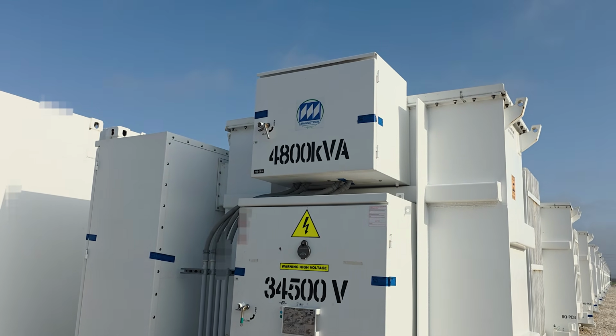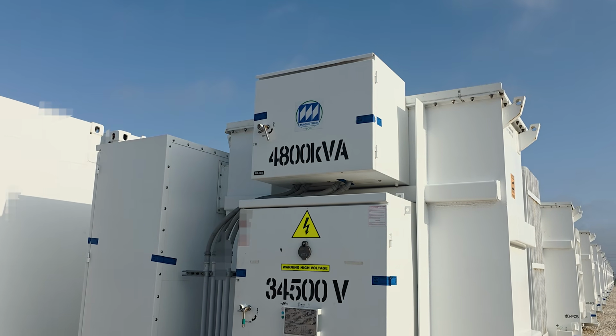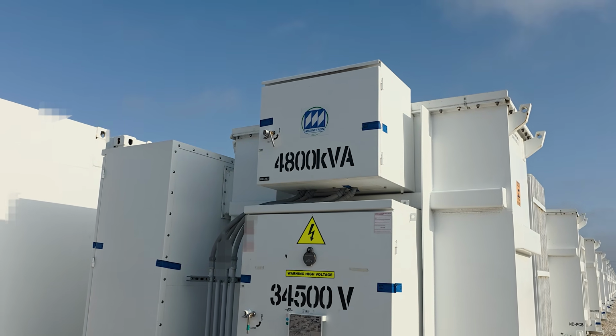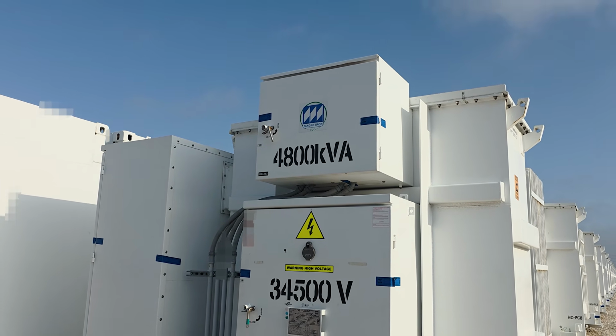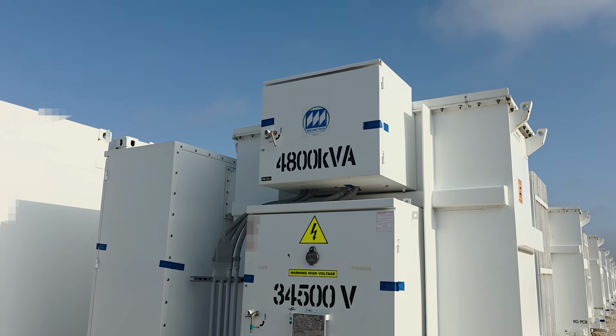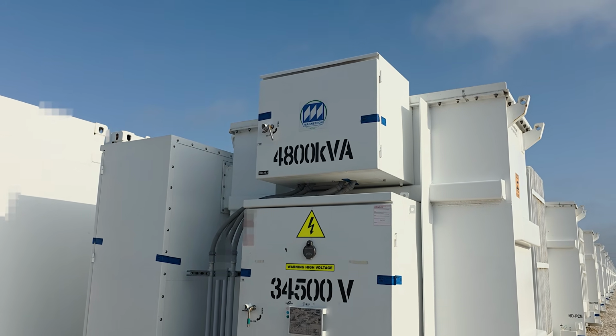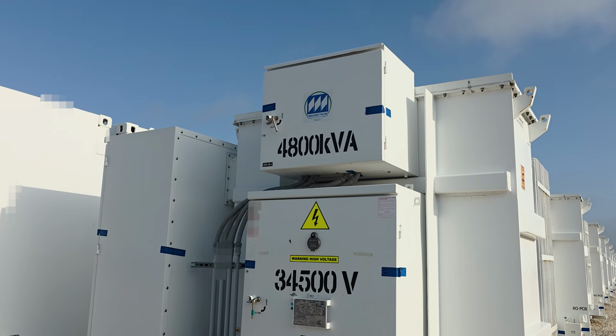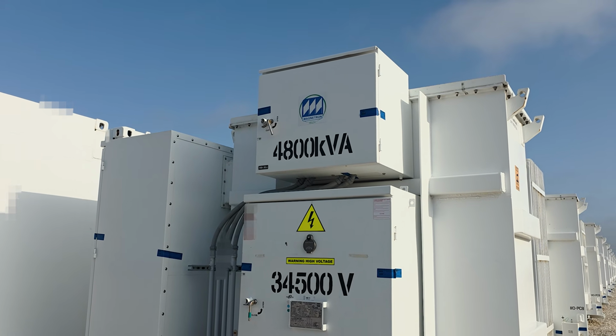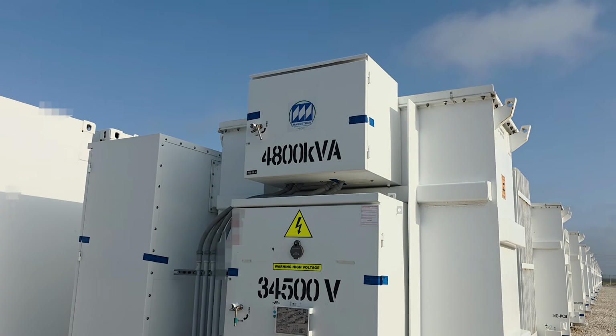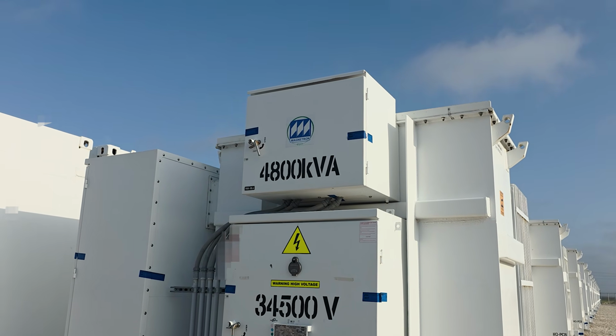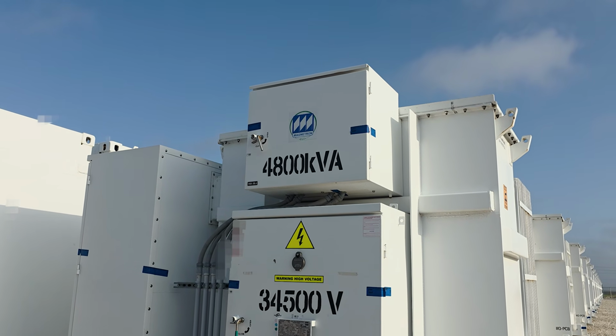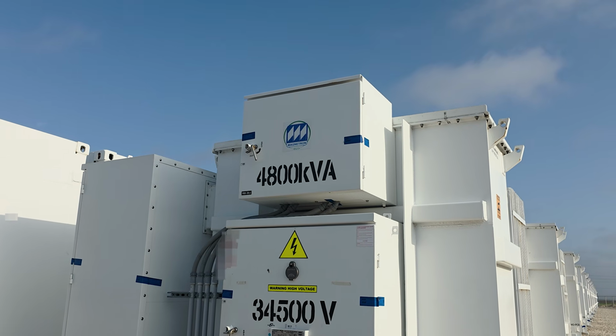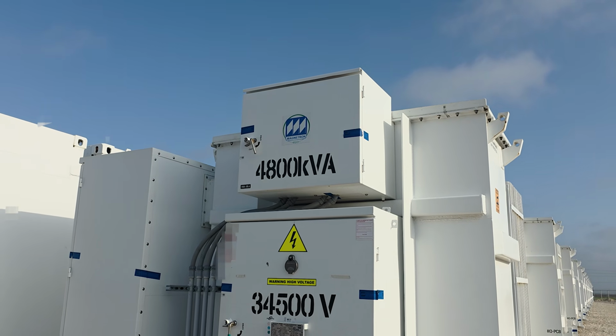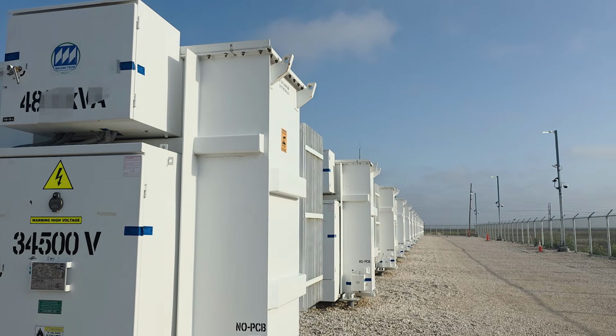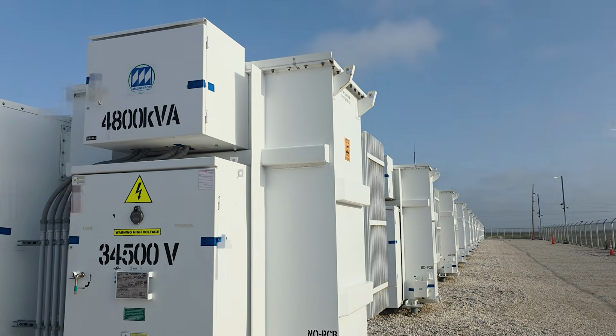This is a little bit different situation. They have added items. You've got your oil level switch attached to normally open, normally closed circuits. So if the oil level reduces down to a certain point, it will automatically shut off. They have monitoring in here. They have, I think, a 735 SEL relay, which will gather individual power data from each transformer and send that data back to the house. That is not normal.